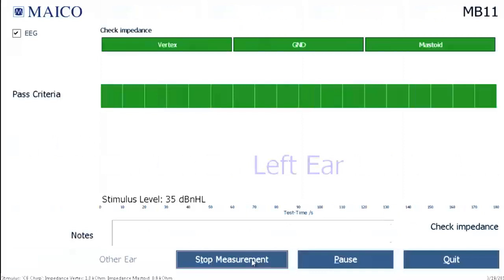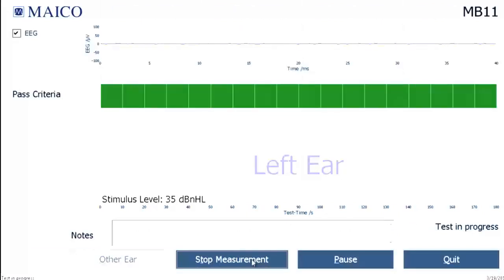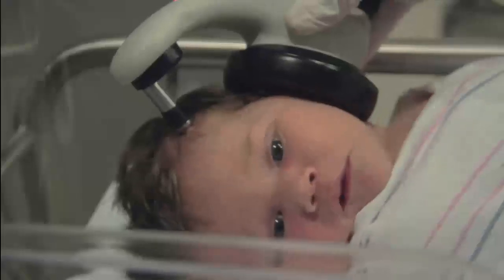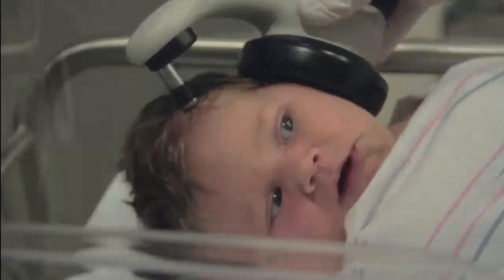After a successful impedance check, the ABR measurement will begin automatically. A line will begin to appear on the time graph. After each 1 second of data sample is collected, a segment of the line will be drawn. The line will be red for the right ear and blue for the left ear. Data samples that contain too much noise will be rejected as artifact, and you'll see that the growth of the line pauses. These artifacts generally occur because the baby is active or because the electrode contact has been lost.